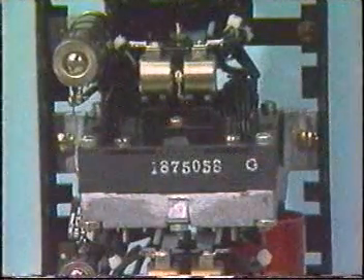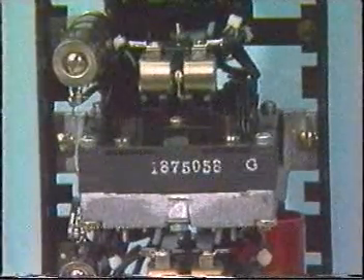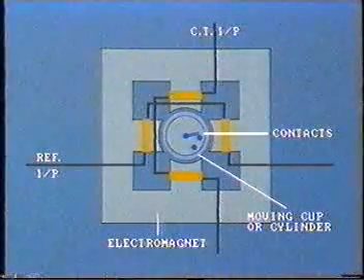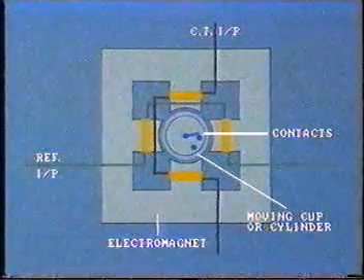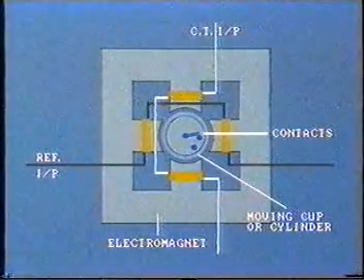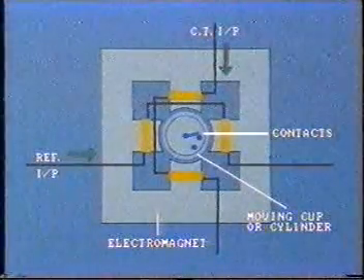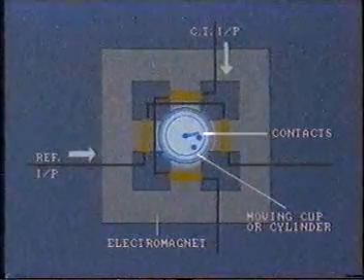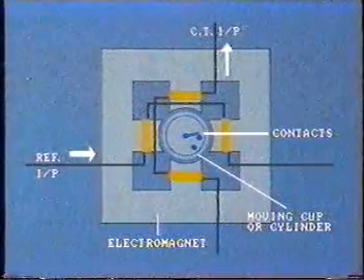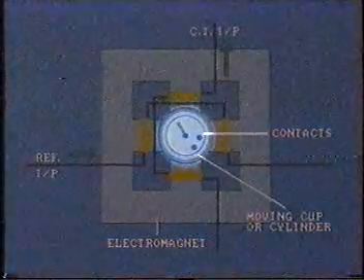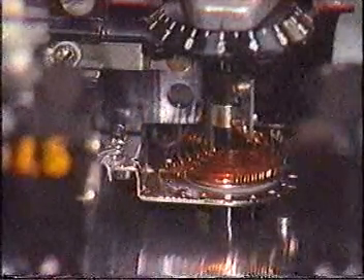One common type of directional relay is the induction cylinder type. The aluminum or copper cylinder takes up a stationary position depending upon the fluxes developed in the electromagnet. One of the coils receives input from the reference voltage or current, while the other receives input from the CT of the protected circuit. When current flow is in the selected non-tripping direction, the two fluxes set up the cylinder so that its contacts block operation. If the flow of primary current reverses, the aluminum cylinder will immediately take up a new position, and its contacts will now allow rotation of the time overcurrent disk, so the relay can operate.